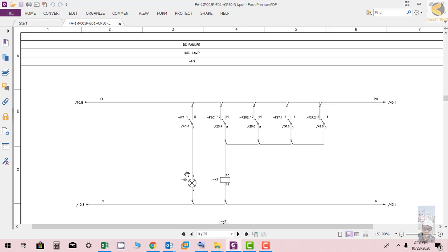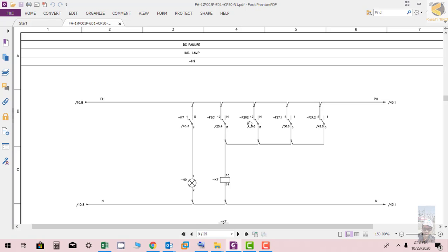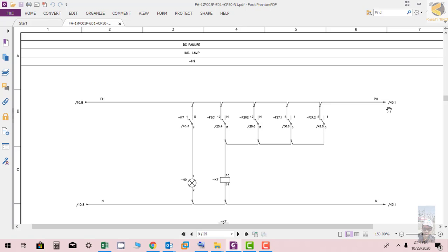Then you can find the K7 relay. K7, this is the contact K7 and it's picked up. K7 will pick up if you can see the DC MCB F201 is switch off or tripped, or F202 MCB switch off or tripped, or you can see the DC supervision relay F27.1 or F27.2, this relay is basically drop-off. I will show you this detail when I will go to this sheet.